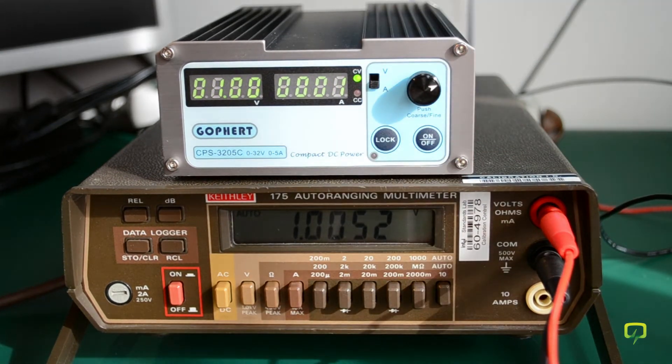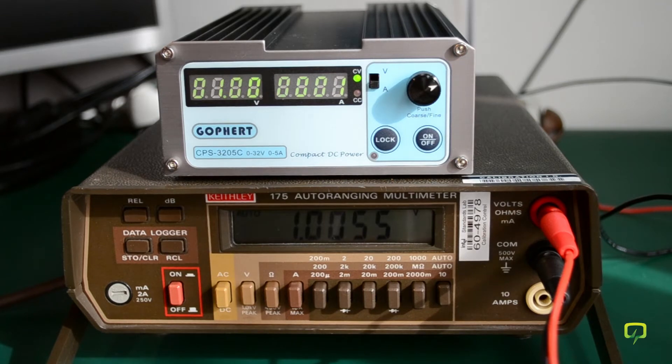And now the unit will go into voltage calibration mode. As a note, you have to calibrate the voltage with no load. I only have the voltmeter connected to the output of the power supply, so that is high impedance. The voltmeter display shows 1.00 and the ammeter display shows 001.